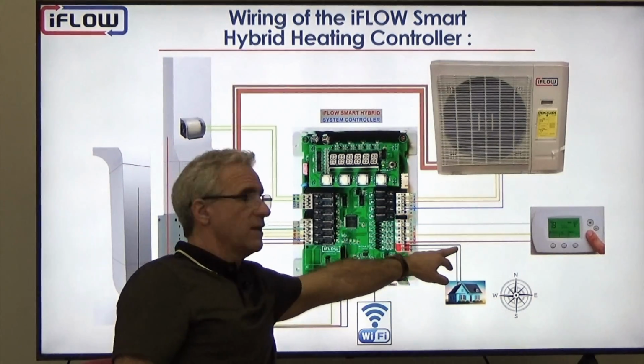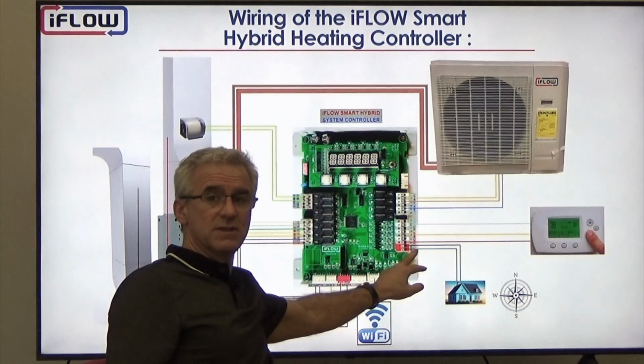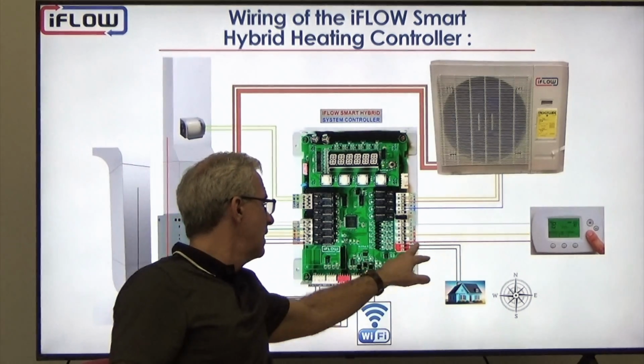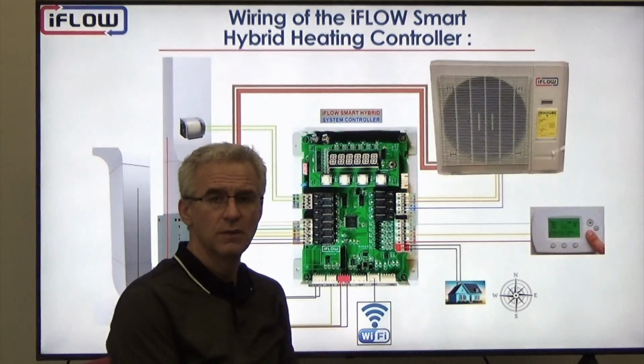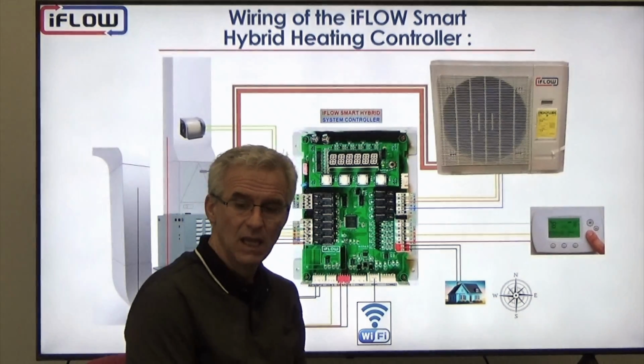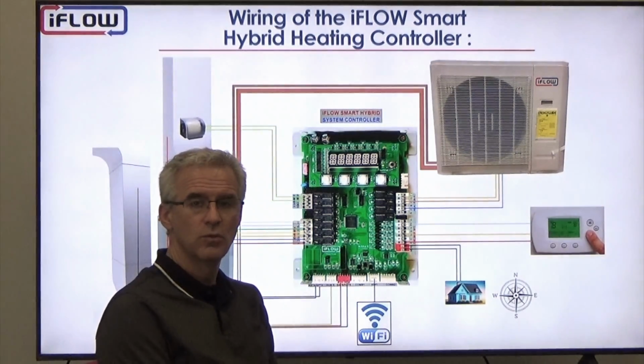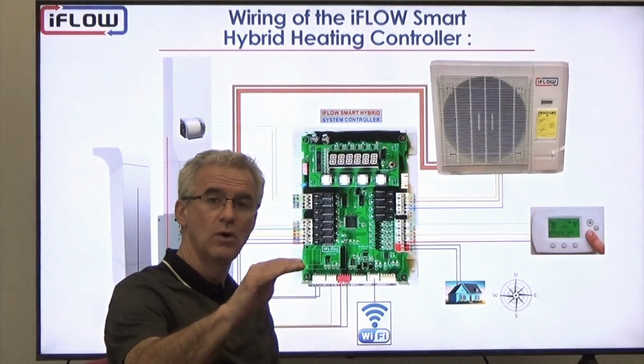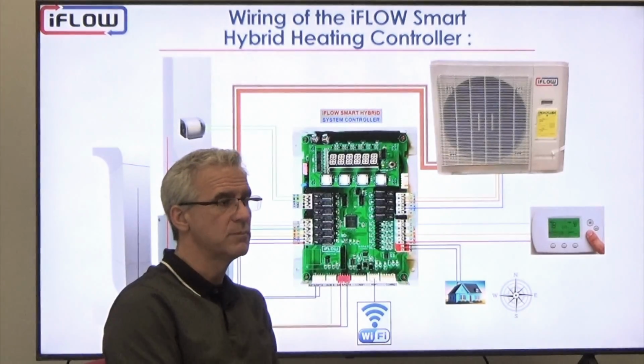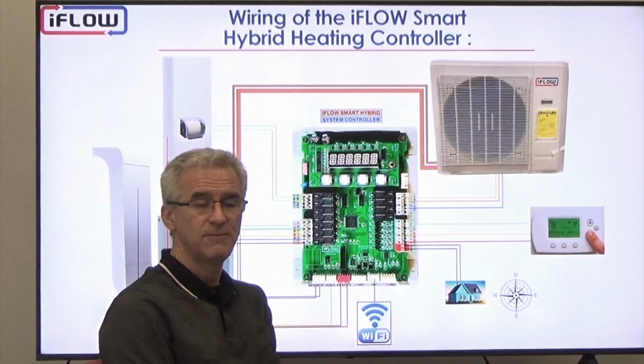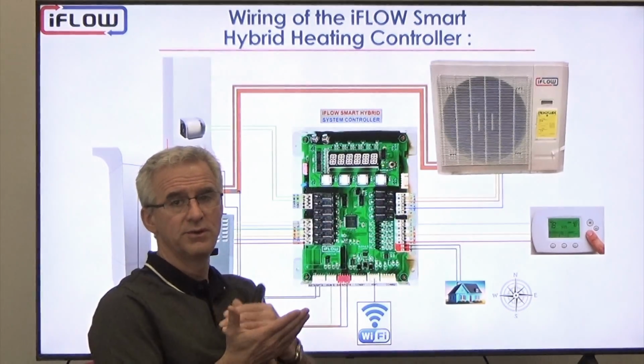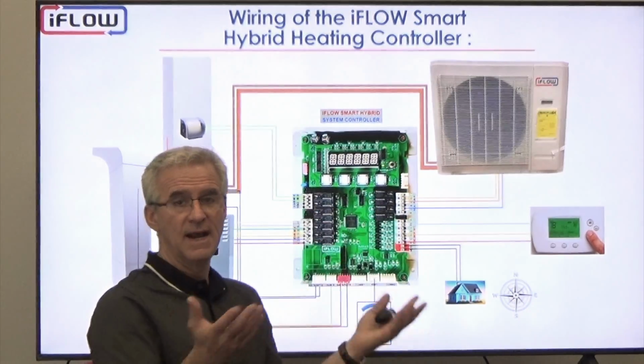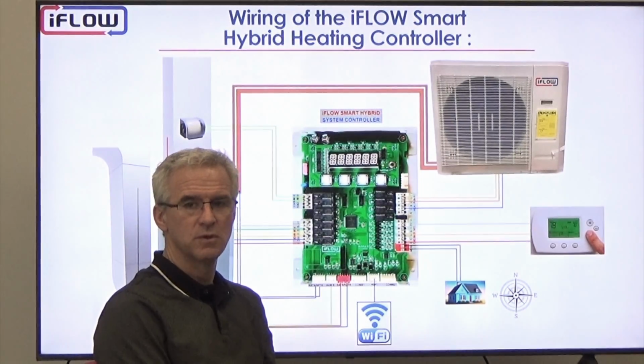We're also going to hook up the outdoor sensor. So again, that's a physical sensor that we connect outside. That should go on the north wall ideally. If not available on the north wall, then on any wall that you can get it on, but preferably not in the sun. If it's in the sun, it's going to read a temperature that's warmer than the actual ambient temperature in many cases.